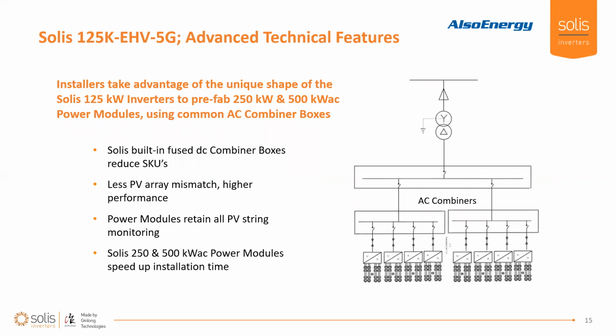Now, you saw that inverter was kind of a unique shape, and we built it that way so that you could prefab some power modules, some 250K or 500K, or even, as you see there, a 1 megawatt setup where you're using 2 AC combiner boxes. You could, for example, mount that on a pad near a centrally located transformer.